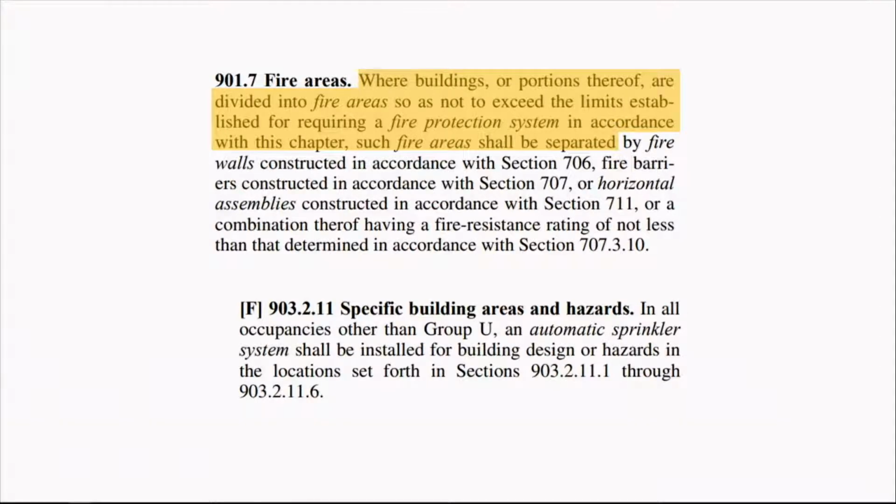And section 903 calls out for every single occupancy some sort of a requirement for how large those areas can be before they must be divided into smaller fire areas, which are fully enclosed, the type of enclosure that the reviewer seems to be asking for, or they need to be sprinkled. That's the gist of 903. Most of those area limitations are 12,000 square feet. Some are less, some have special exceptions, some have special requirements. Every single occupancy group has some specified limit except for Group U.